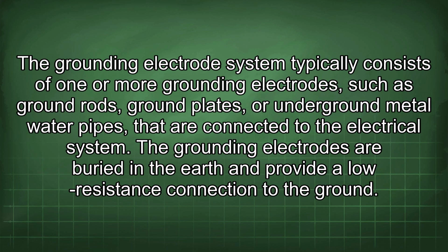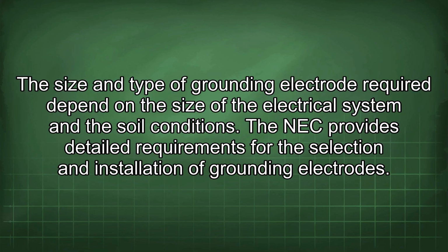The grounding electrode system typically consists of one or more grounding electrodes, such as ground rods, ground plates, or underground metal water pipes, that are connected to the electrical system. The grounding electrodes are buried in the earth and provide a low-resistance connection to the ground. The size and type of grounding electrode required depend on the size of the electrical system and the soil conditions. The NEC provides detailed requirements for the selection and installation of grounding electrodes.